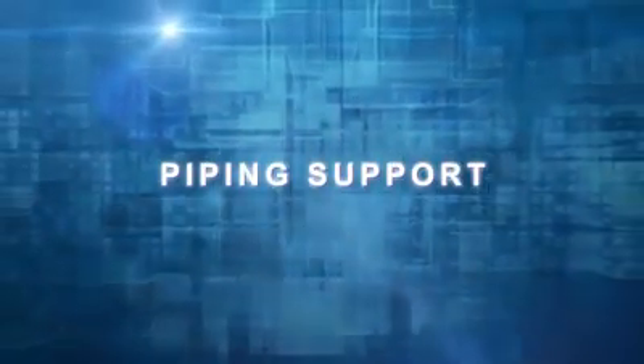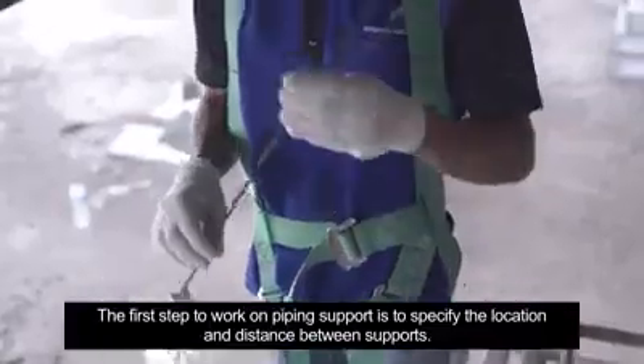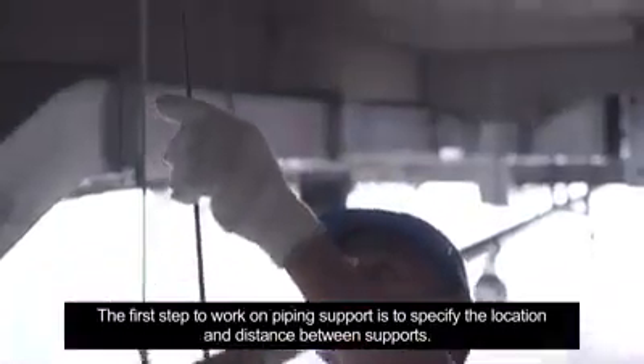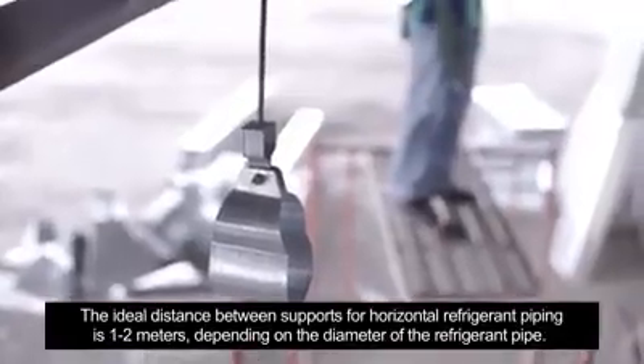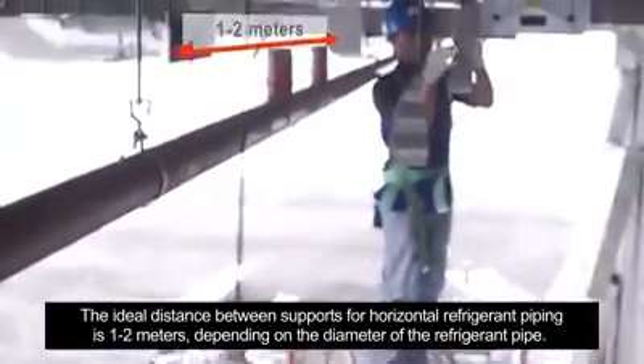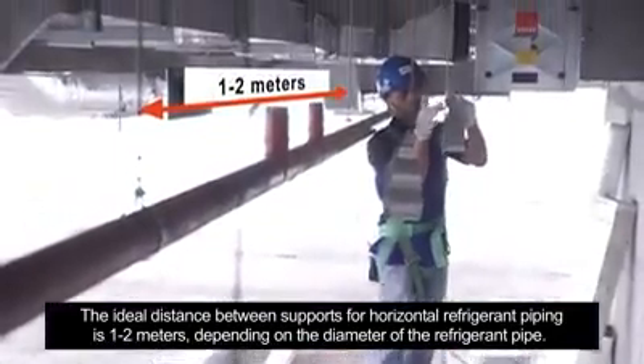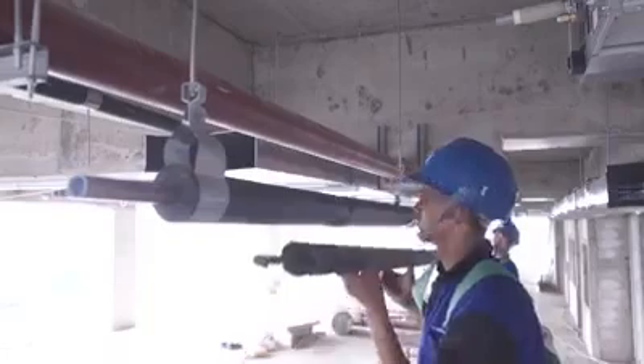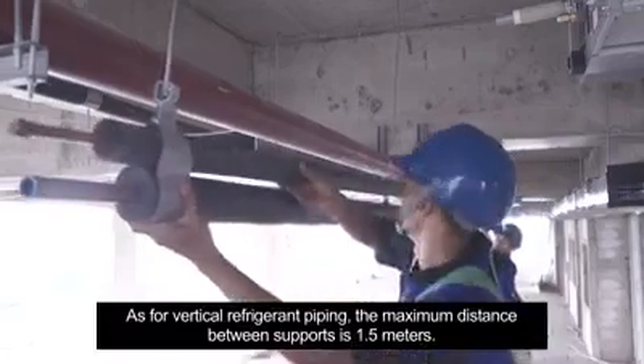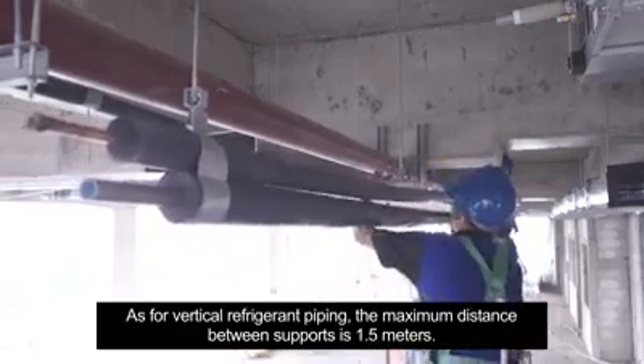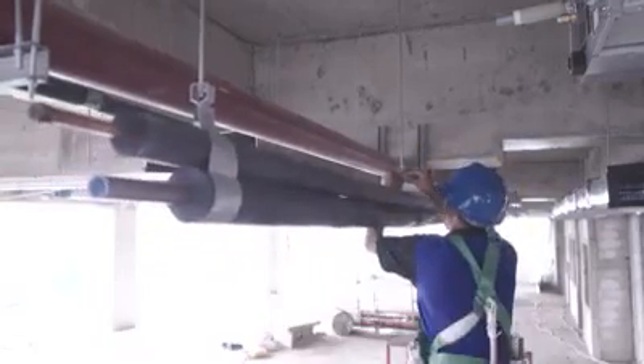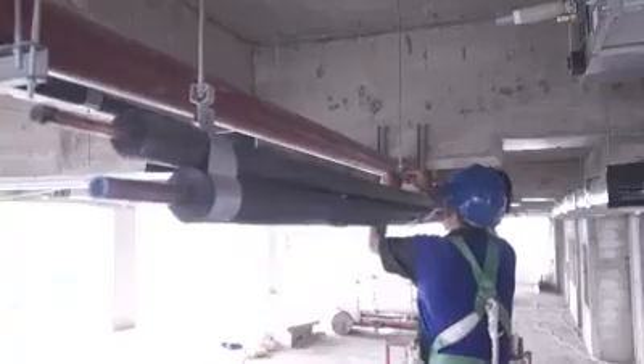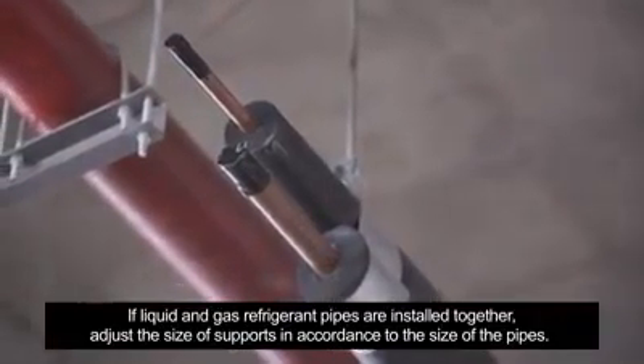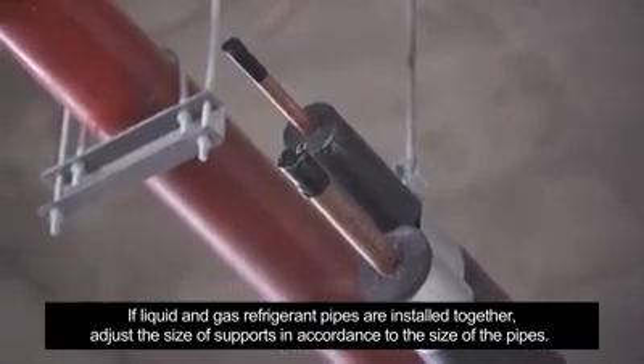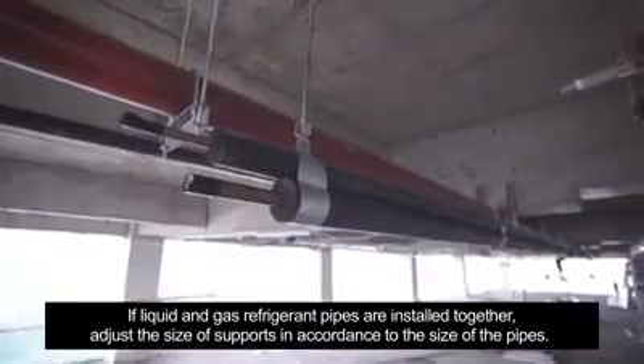Piping support. The first step to work on piping support is to specify the location and distance between supports. The ideal distance between supports for horizontal refrigerant piping is 1 to 2 meters, depending on the diameter of the refrigerant pipe. As for vertical refrigerant piping, the maximum distance between supports is 1.5 meters. If liquid and gas refrigerant pipes are installed together, adjust the size of supports in accordance to the size of the pipes.